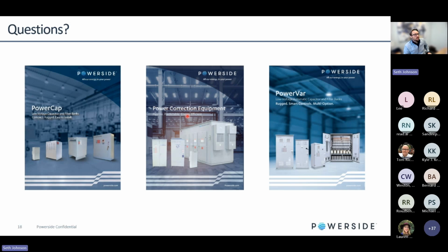Yeah, you'll see that with smaller solar arrays. One of the things about inverters is that they're actually capable of providing reactive power compensation. However, you're not going to use a solar inverter to do reactive power compensation when ultimately you want it to provide real power out. So we have seen that as well.